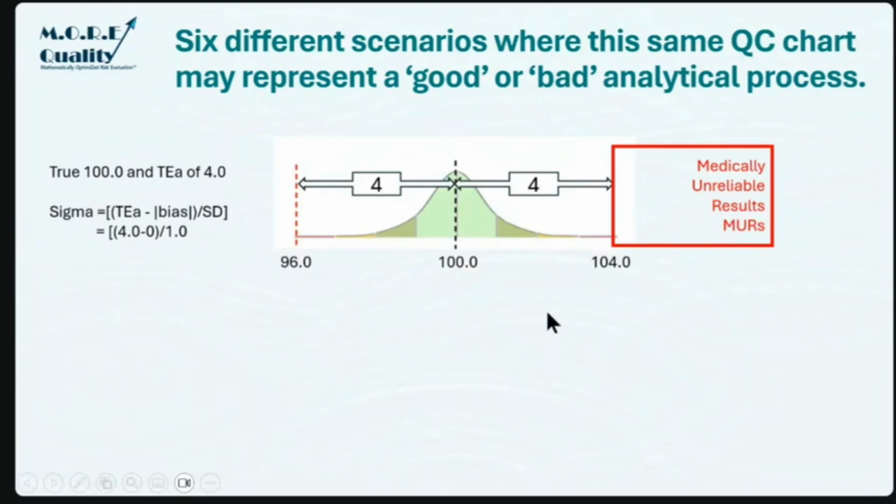What that means when you know that the sigma value is 4, is that if this mean shifted 4 standard deviations, 50% of your patients would fall over the cliff of extreme risk. 50% of your patients would be exposed to unacceptable risk if you shifted by the full sigma metric. The question is, how many SDs can you shift? And that's not one that's commonly answered.